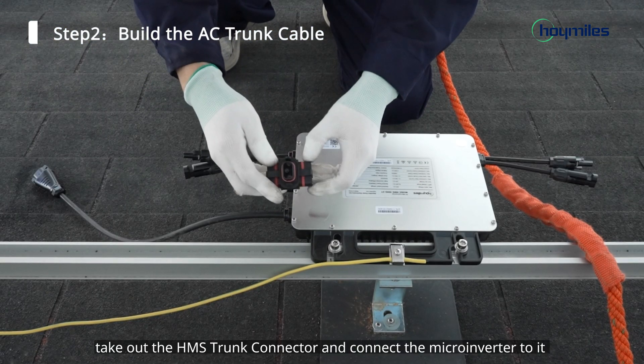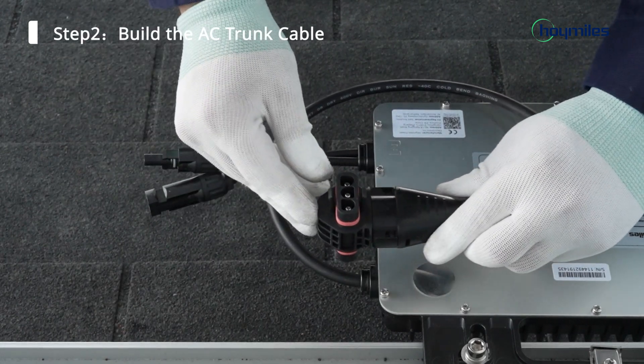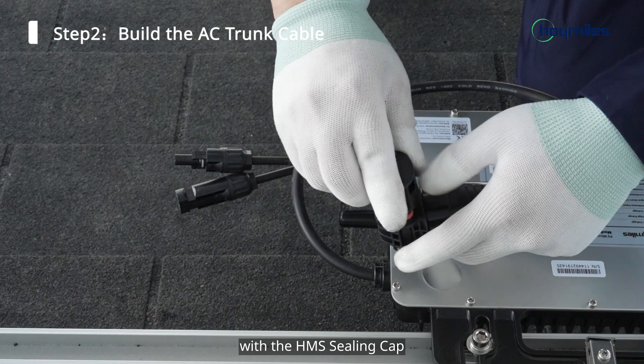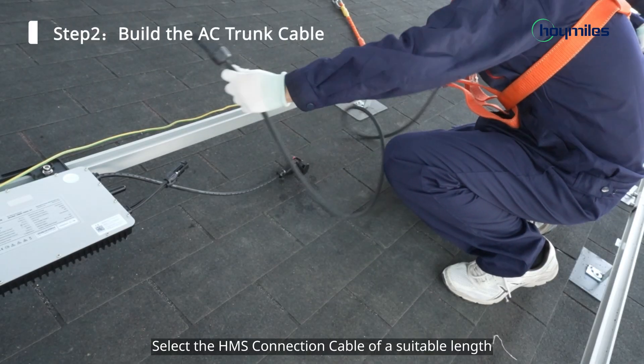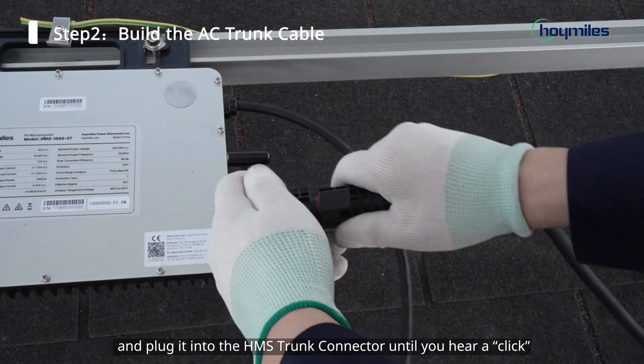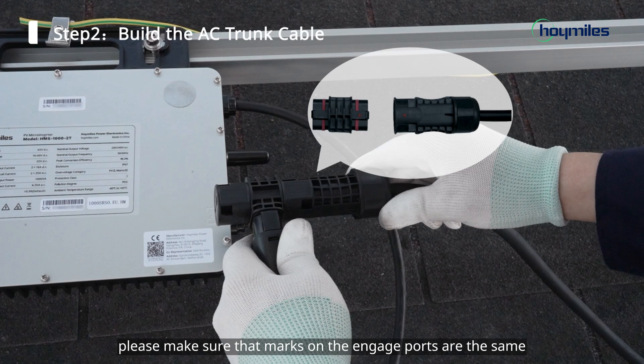Next, take out the HMS trunk connector and connect the microinverter to it until you hear a click. Then cover the unused end with the HMS sealing cap. Select the HMS connection cable of a suitable length and plug it into the HMS trunk connector until you hear a click. When connecting the HMS connection cable and the HMS trunk connector, please make sure that the marks on the engaged ports are the same.